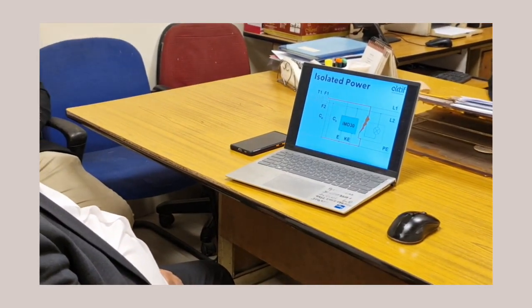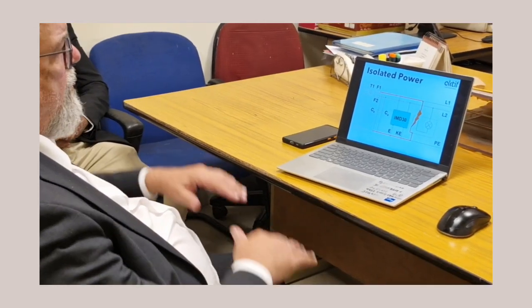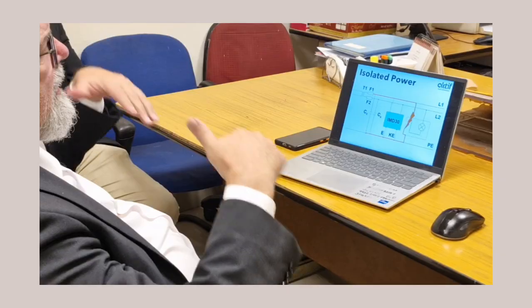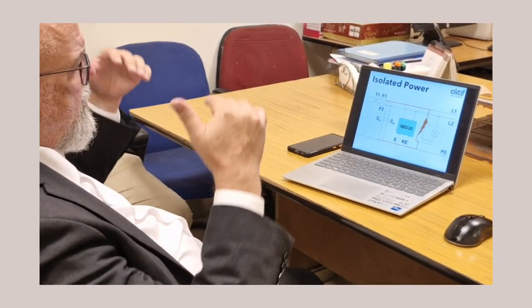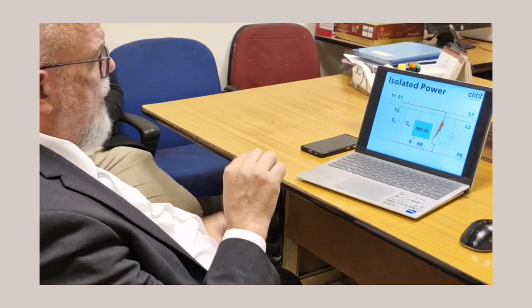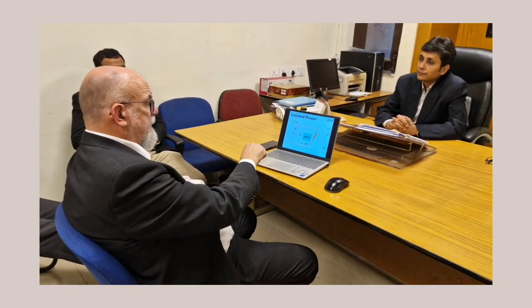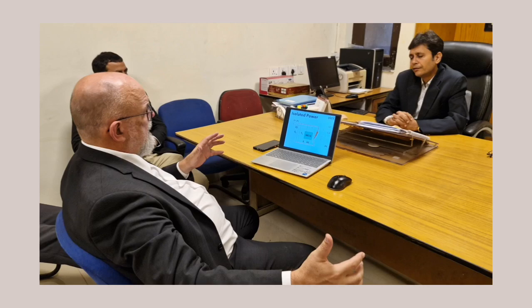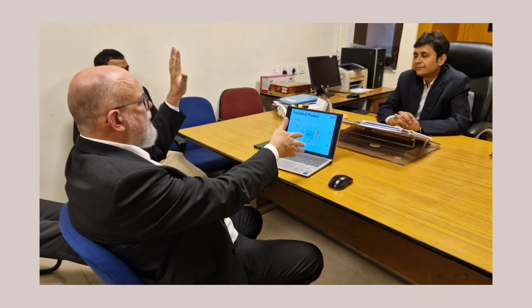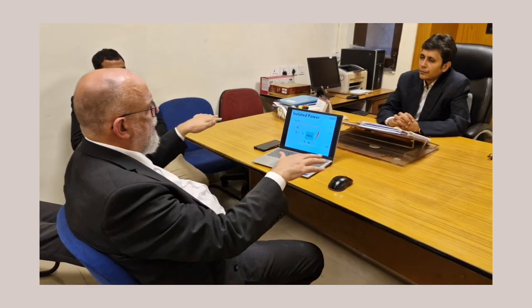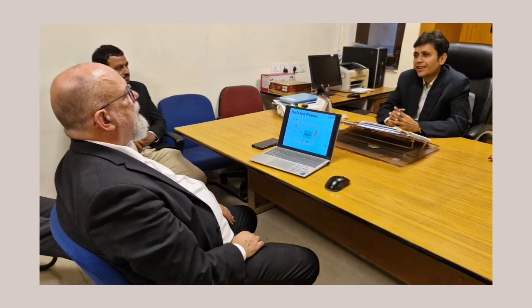In this case, when there's an electrical fault, these IMD devices give an alarm when there is some problem. The standard clearly says that when there's no problem, you have a green light. When there's an alarm, you have to show a yellow light and a buzzer has to sound. This sound is allowed to be silenced, and this alarm will come at the location of the IMD, which is normally outside the operating room. That's why inside the operating room we have a remote alarm unit which tells the nurses and the doctor there's an electrical problem, but continue, don't stop working. But we have to depute someone to attend that fault so that it does not continue.